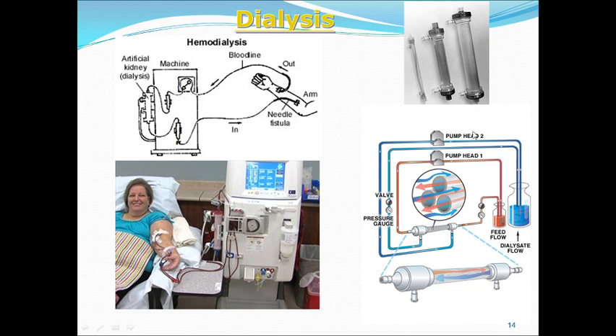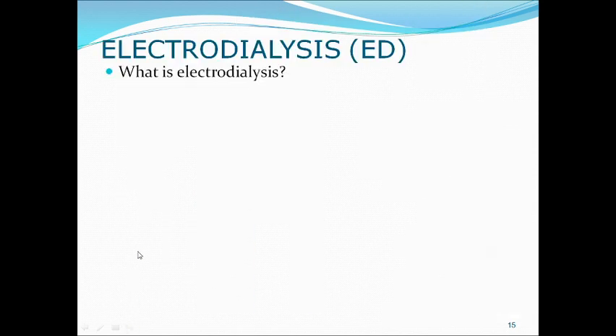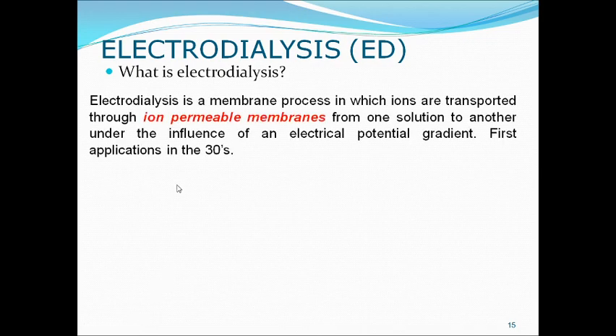Blood goes through pump head 1 and pump head 2, and a filter system is there. It looks complicated, but the principle is very, very simple — it filters the blood, removes urea and creatinine as unwanted materials. They are separated and collected in the machine, and purified blood is once again reinserted into the patient. Another concept is electrodialysis — if you apply electrical current, then dialysis is referred to as electrodialysis — with ion permeable membranes where you create anions and cations in the system.